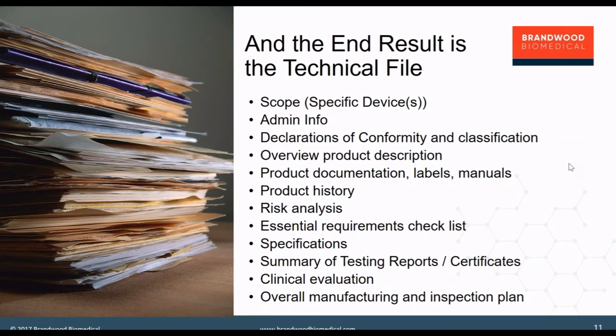Essential requirements checklist, we've talked about that before. Obviously, this is your primary evidence prior to putting together your declaration of conformity. So you should only sign your declaration of conformity once you've satisfied yourself that all the essential requirements have been met for the specific product. So that's the key regulatory document to be included in the technical file here.